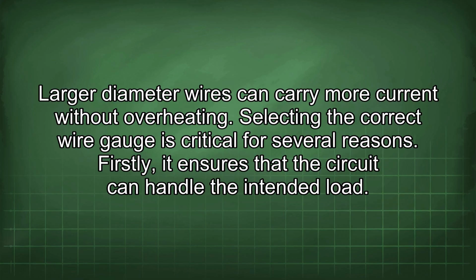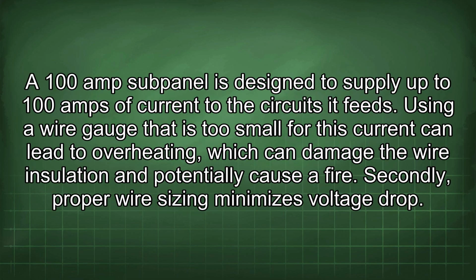Selecting the correct wire gauge is critical for several reasons. Firstly, it ensures that the circuit can handle the intended load. A 100 amp subpanel is designed to supply up to 100 amps of current to the circuits it feeds. Using a wire gauge that is too small for this current can lead to overheating, which can damage the wire insulation and potentially cause a fire.